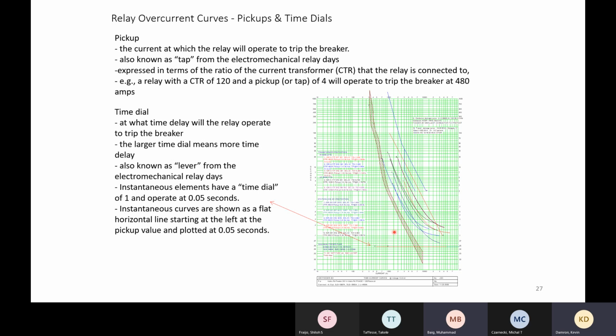So, Kevin, can I ask a question here? Yeah. What I understood from the discussion board is that there is no coordination for the instantaneous element relays. I'm not fully understanding that part. If there is no coordination for the instantaneous element, then why are we using them? We also studied that it works based on the impedance. The farther we go, the higher the impedance, so the flow of current will be different at different points of the circuit down the road as you get away from the source. So can we still have coordination using the instantaneous element with the impedance change down the line, or can we not have any coordination literally with the instantaneous element, and why are we using it then?